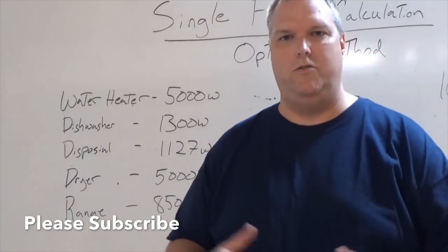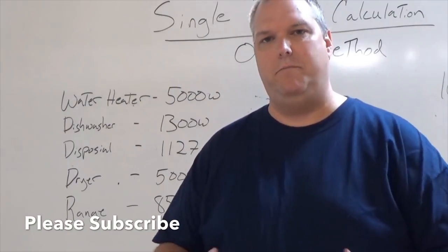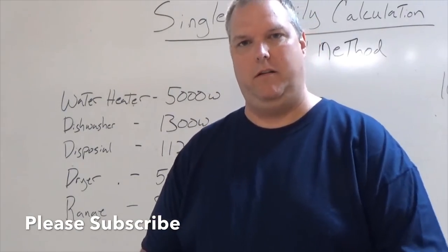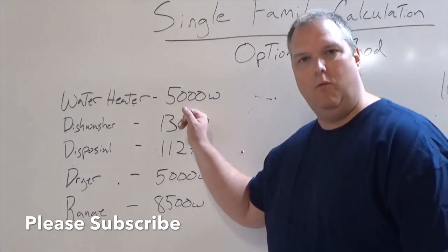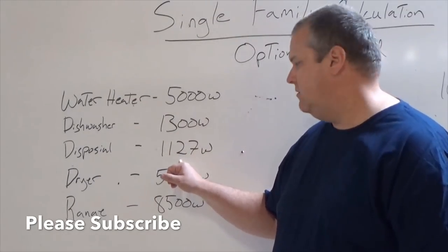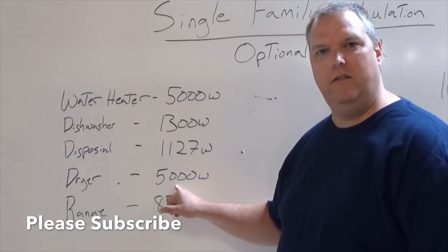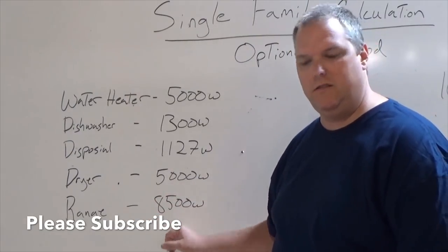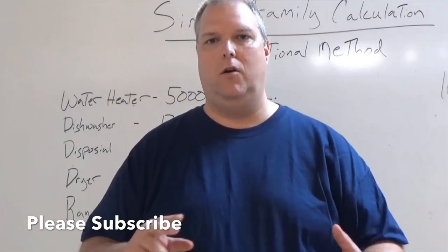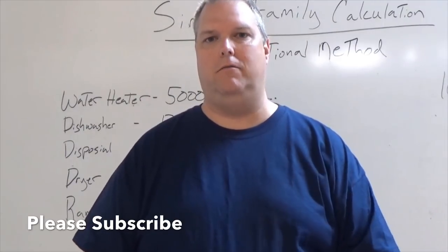Just like in the standard method, we go through everything that's going to be installed in the dwelling. We have a hot water heater at 5,000 watts, a dishwasher at 1,300 watts, a disposal at 1,127 watts, a dryer at 5,000 watts, and a range at 8,500 watts. Note that at this point we are not adding any heating, cooling, or largest motor — that's covered in another step.